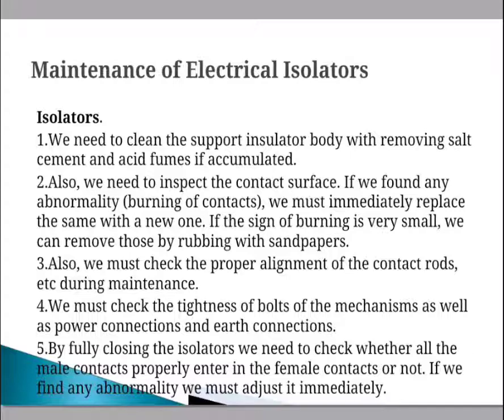Check the proper alignment of the contact rods during maintenance. Check the tightness of the bolts of the mechanism as well as power connections and earth connections. By fully closing the isolator, verify that all male contacts properly enter the female contacts — if any abnormality is found, adjust it immediately.